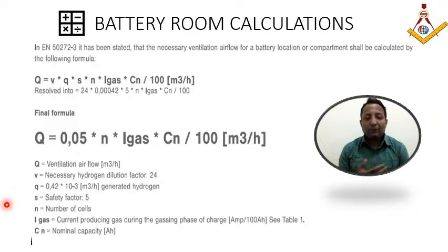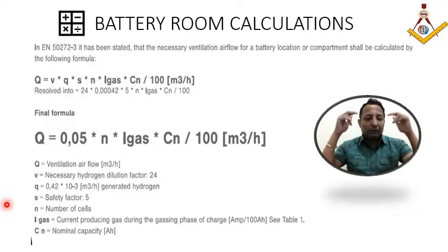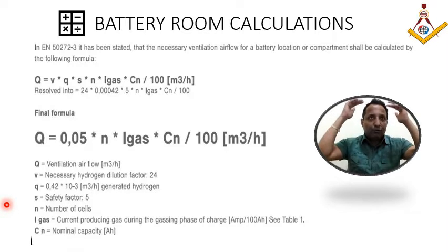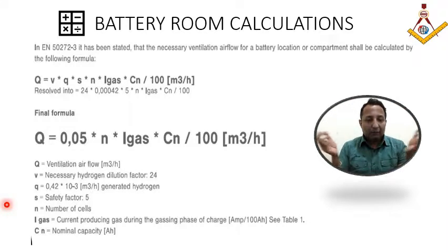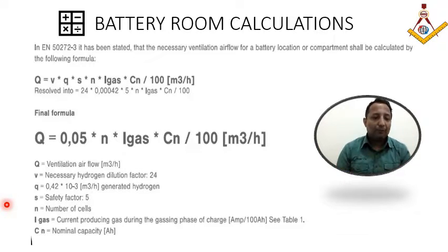So since the hydrogen is getting released, and hydrogen gas is always lighter in nature, it gets accumulated over the ceiling. For that we need to provide fans which are duty standby, suitable for hazardous areas, and the ducting always goes at the roof side, roof type. It touches the roof, and the suction happens from the side or from the bottom. So it takes care of the hydrogen gas which is getting accumulated at the top.